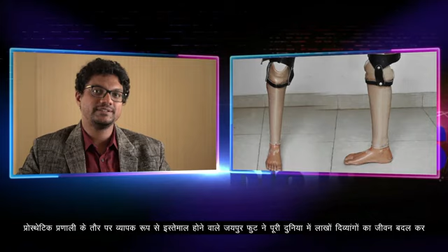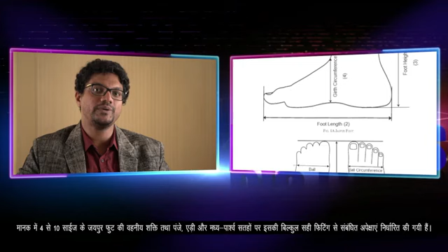Jaipur foot, which is widely used as a prosthetic system, has transformed the lives of hundreds of thousands of amputees all over the world by providing them with mobility and dignity. This Indian standard IS 17034 covers the dimensions and other requirements of Jaipur foot. This prosthesis is hand fabricated using locally available raw materials of variable quality and fitted on the amputee. The dimensions and tolerances of the Jaipur foot for sizes 4 to 10 and the correct fitment of its shape in toe, heel and mediolateral surfaces are provided in this standard.